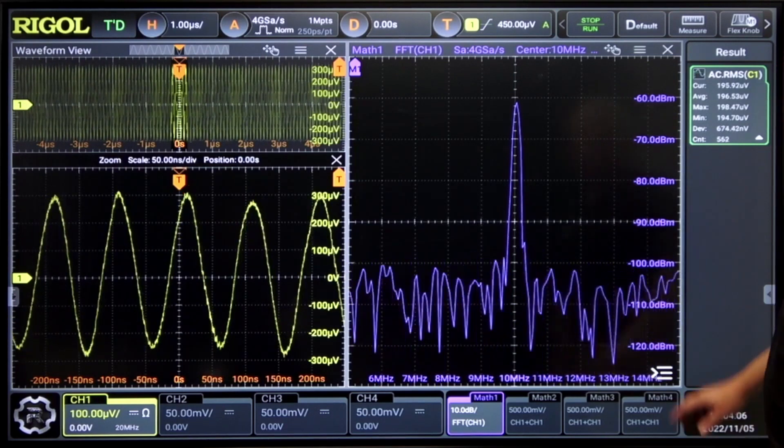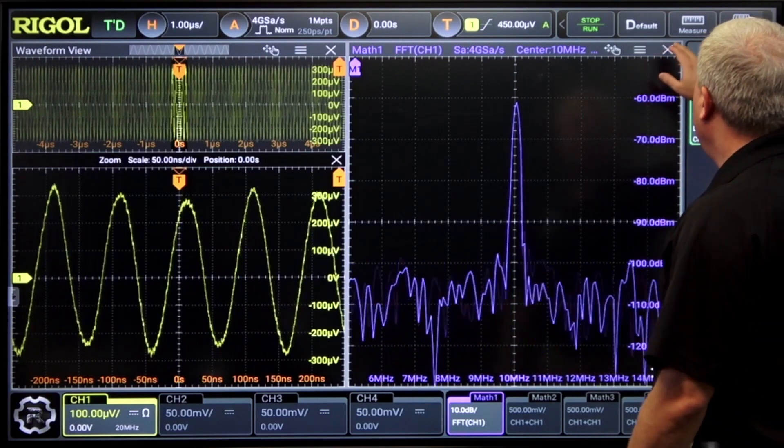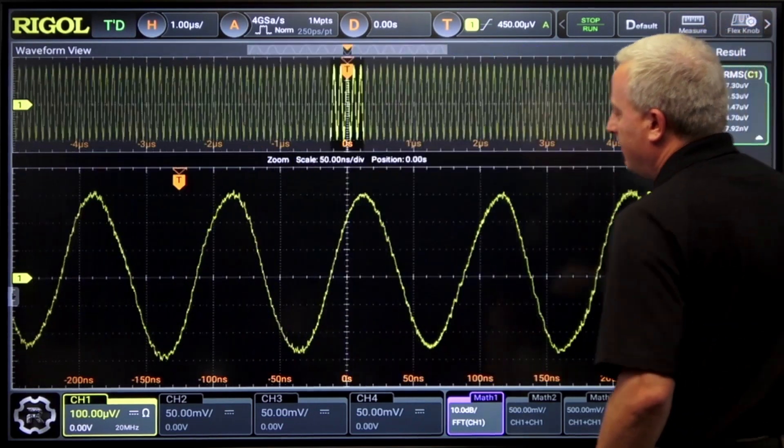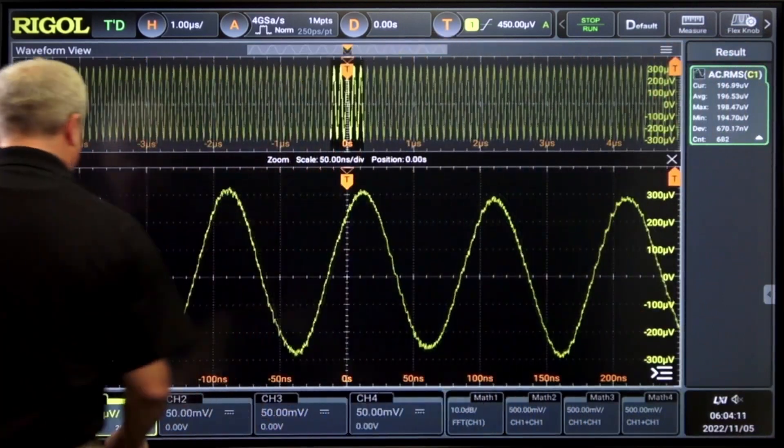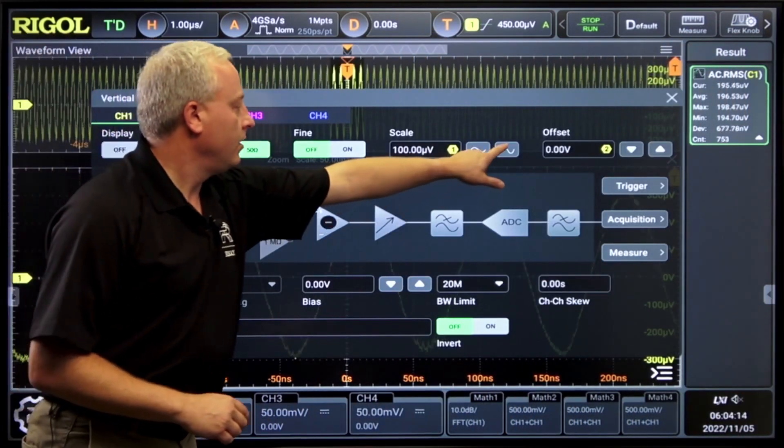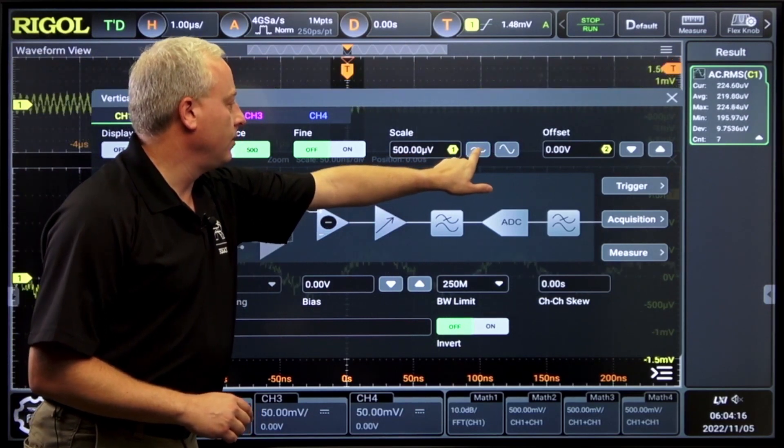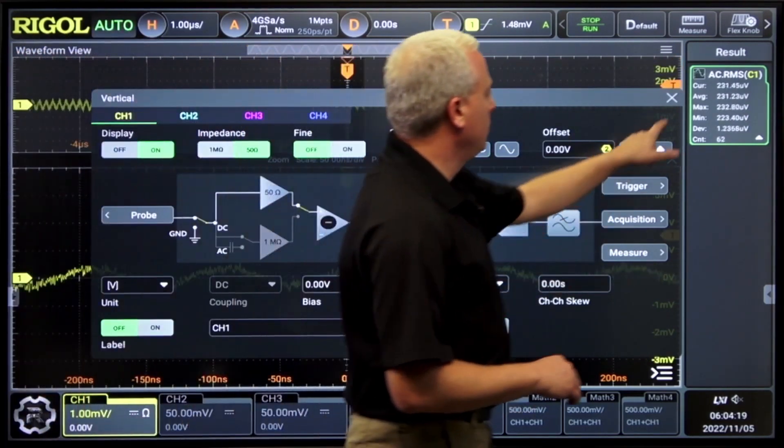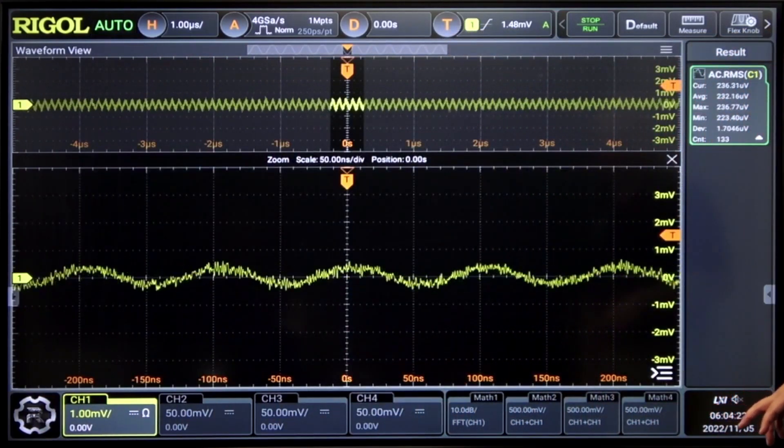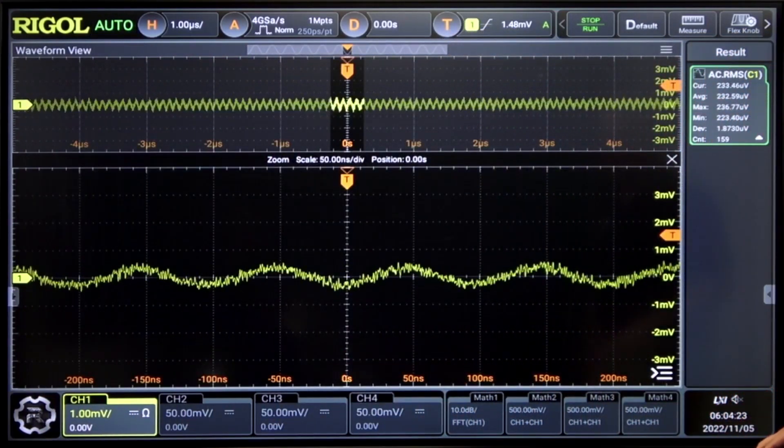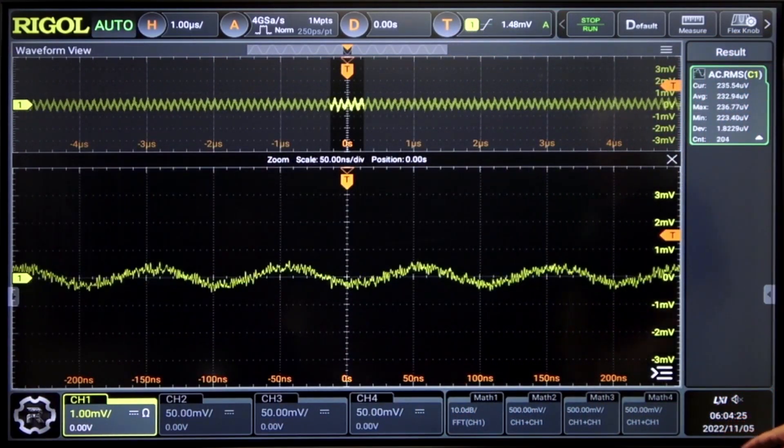One of the other great capabilities here is to look at the high resolution in a little different way. So to do that, let's go up to the one millivolt range where we have full range on the bandwidth.